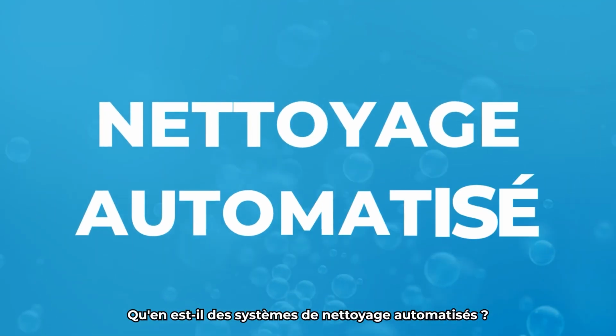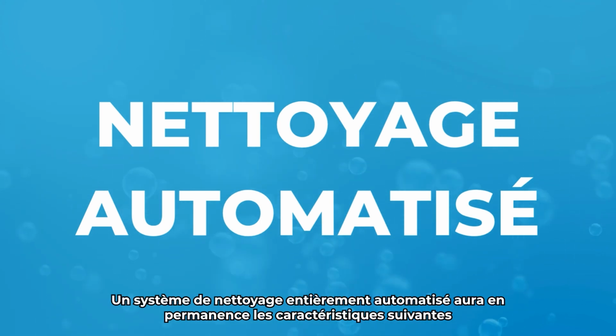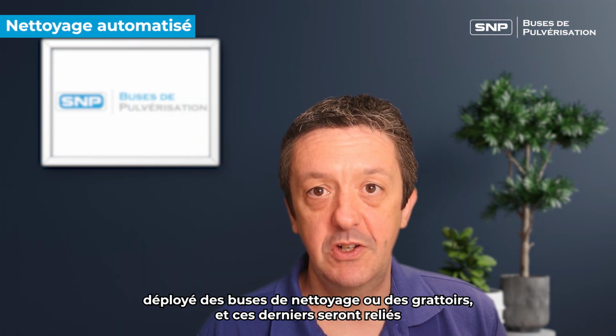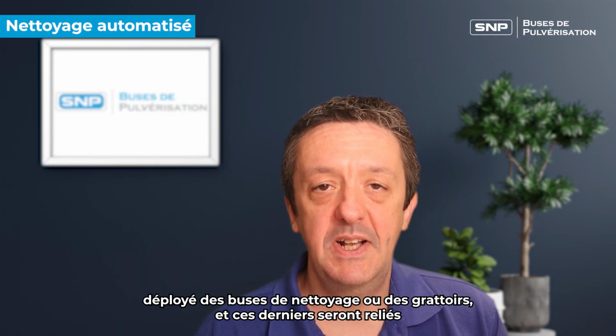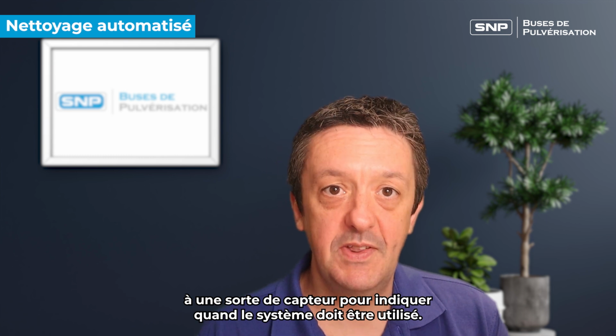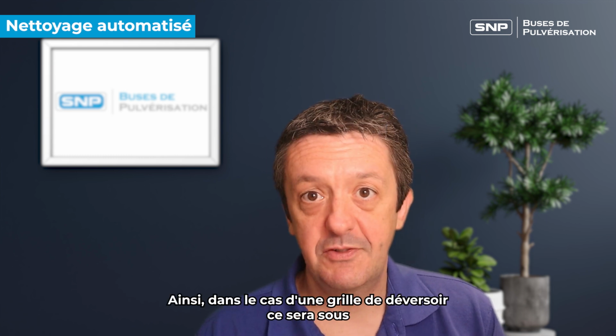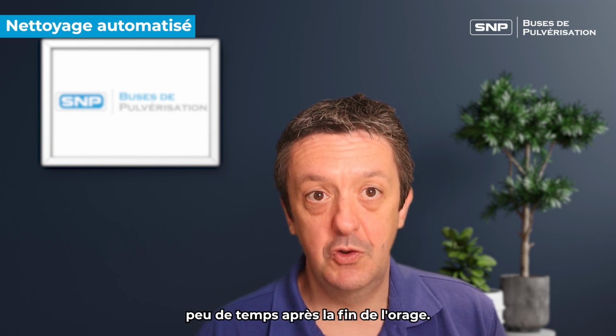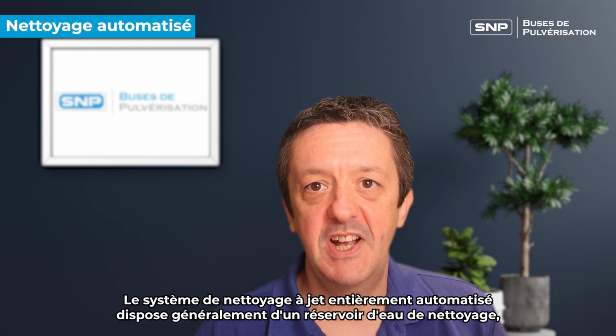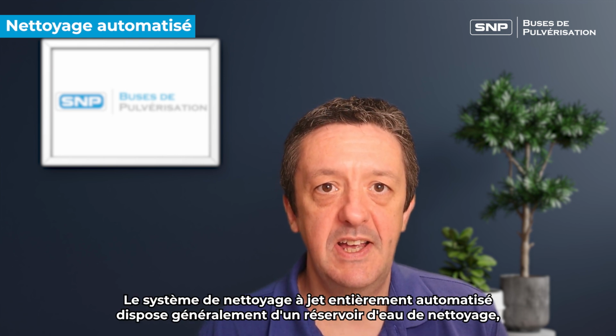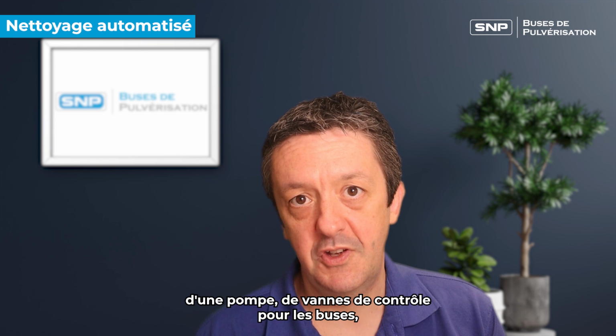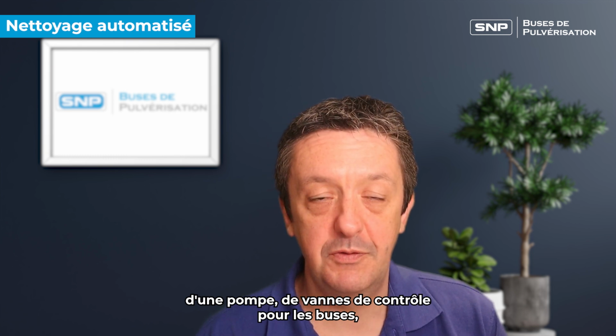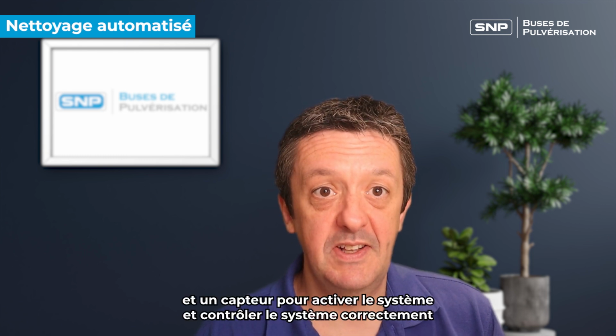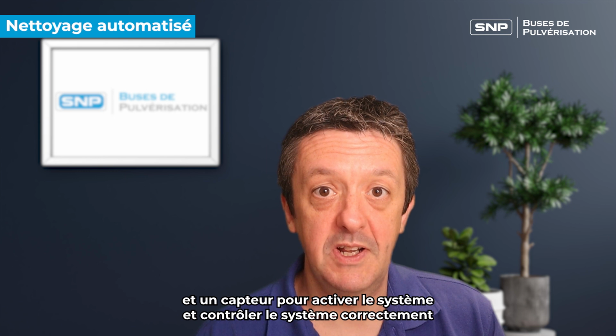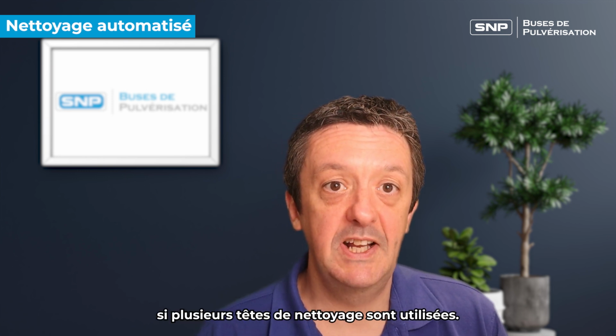What about automated cleaning systems? So a fully automated cleaning system will have permanently deployed washing nozzles or scrapers, and these will be linked to some kind of sensor to indicate when the system needs to be operated. So in the case of a CSO screen, this will be shortly after the storm event has finished. The fully automated jet cleaning system would typically have a wash water storage tank on site, a pump, control valves for the nozzles, and a sensor to activate the system and control the system properly to sequence the nozzles if multiple cleaning heads are used.